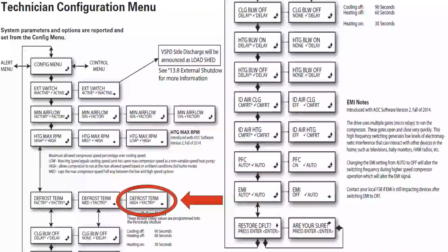Factory defrost termination terminates at 47. So what that means, for defrost to engage, the outdoor temperature has to be below 52 and the coil temp has to be below 32. So it's referencing the coil temperature at 32 degrees. Once it initiates defrost, that coil temperature needs to reach 47 degrees. And what we've seen is that 47 degrees doesn't get all the ice off in our area.